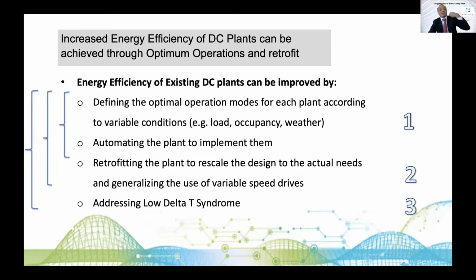The second lever, of course, is sometimes generalizing the speed drives. Not all the district cooling plants have VFDs on most of the equipment. Very few have VFDs on the compressors. Some have that on the chilled water distribution network, but not all of them have that, for instance, on the cooling towers or condenser water pumps. And we think that with the combination of the optimum parameters, live calculation of optimum parameters, and the retrofit, we can really increase the efficiency by a very important number that we will share with you in a minute.